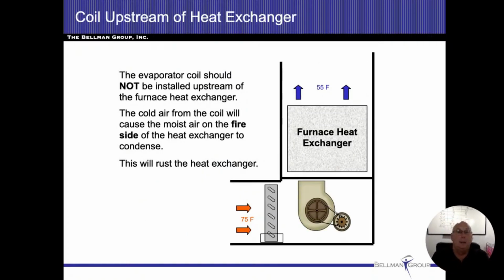Watch for the coil if somebody does install this upstream of the heat exchanger. Now we're going to be adding moisture and humidity onto the heat exchanger. That is going to be creating a problem. We just can't do it. So again, it's filter, fan, heat exchanger, air conditioning coil. In this diagram, we're showing air conditioning coil, then the blower fan and the heat exchanger, and that just would be wrong.